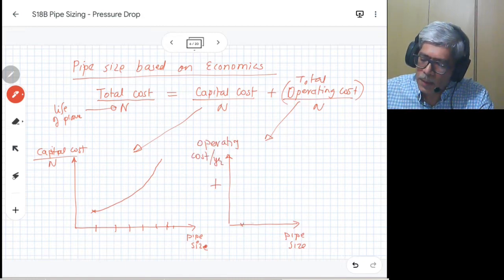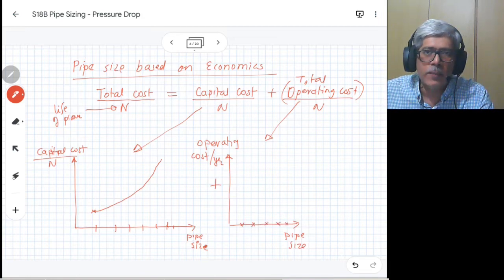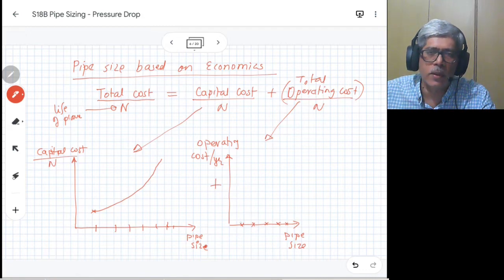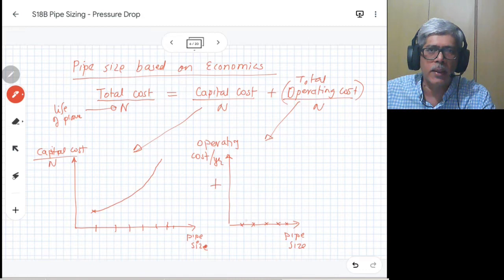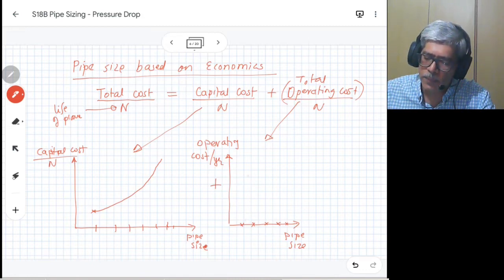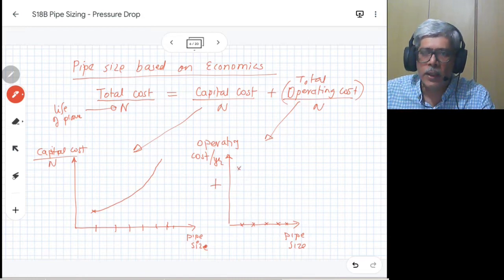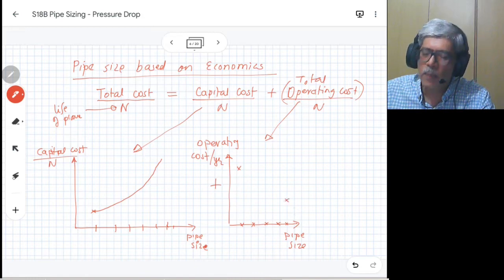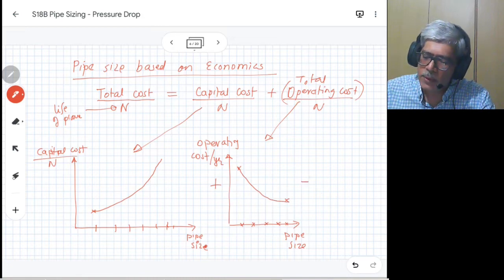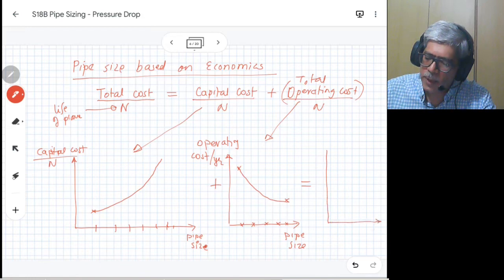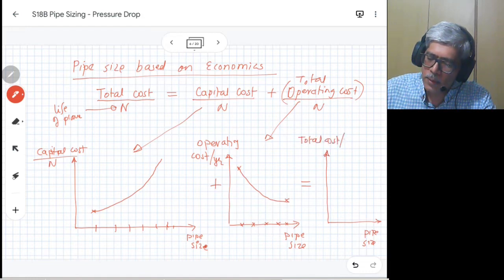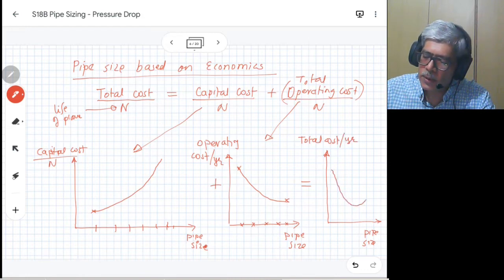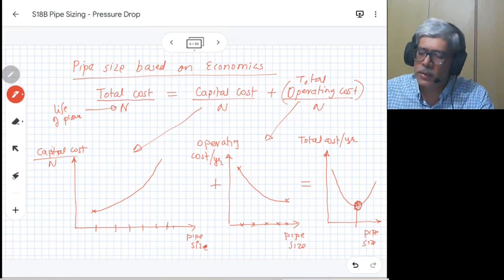Whereas if you consider the operating cost — the cost for running the plant — and plot it against pipe size, for smaller pipe size you have more pressure drop and more resistance. To overcome that pressure drop you require bigger energy, a bigger compressor, a bigger pump, so smaller pipe size means higher operating cost. As pipe size increases, operating cost drops. So you have a reverse curve. If you add capital cost and operating cost together, you get a total cost curve versus pipe size.